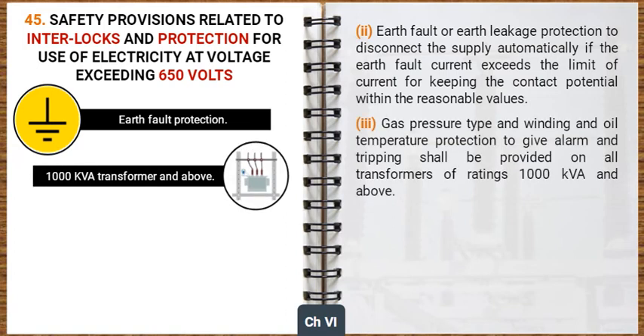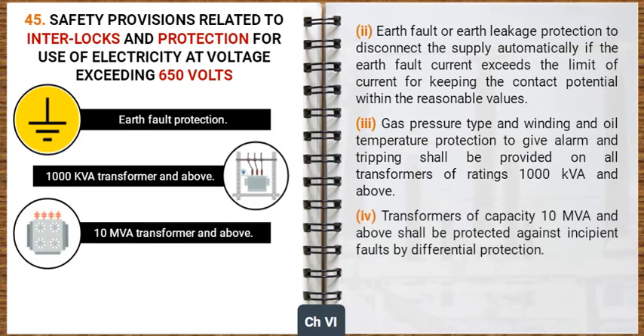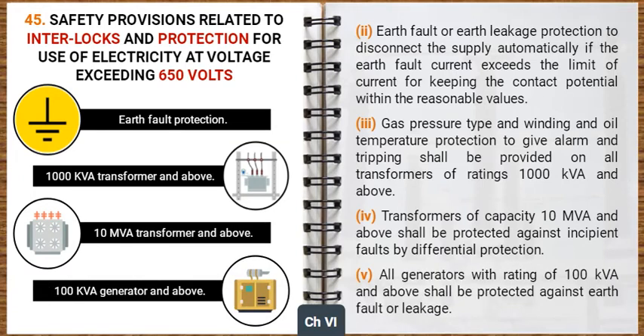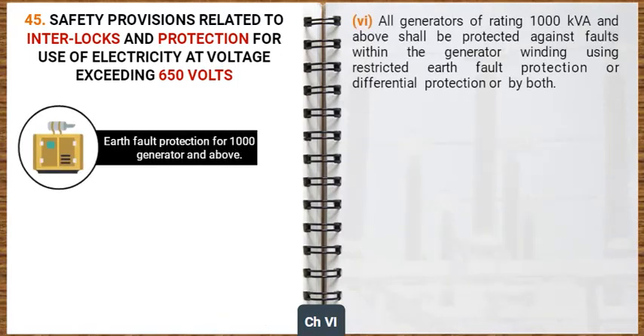Gas pressure type and winding and oil temperature protection to give alarm and tripping shall be provided on all transformers of rating 1000 kVA and above. Transformers of capacity 10 megavolt ampere and above shall be protected against incipient faults by differential protection. All generators with rating of 100 kVA and above shall be protected against earth fault or leakage. All generators of rating 1000 kVA and above shall be protected against faults within the generator winding using restricted earth fault protection or differential protection or by both.